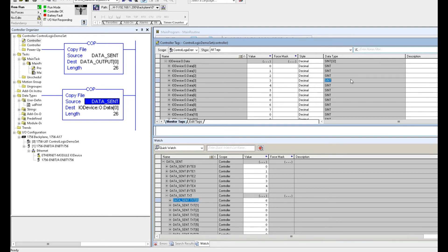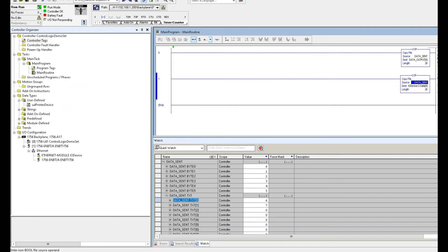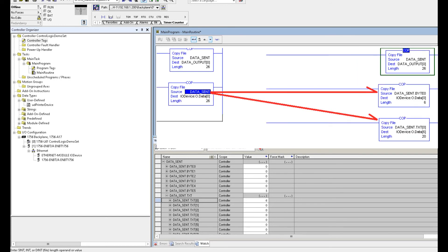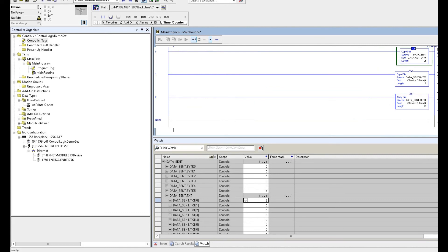If you don't know the rule of this, it's really hard to find this problem and very easy to cause it. Ideally, when we use the COP command, the best way is that the source and the destination — their structure and data type — must be the same. If it's not the same, it will create a problem like this. To solve this problem, we should separate the copy operations to keep the source and destination the exact same structure and data type. We separate this and first write the six bytes from zero to five, then separately handle the sent.text.